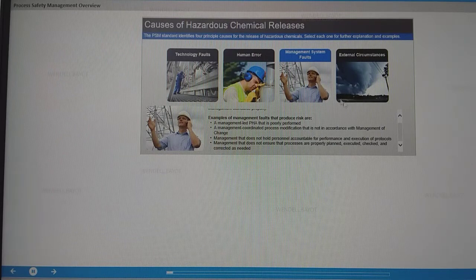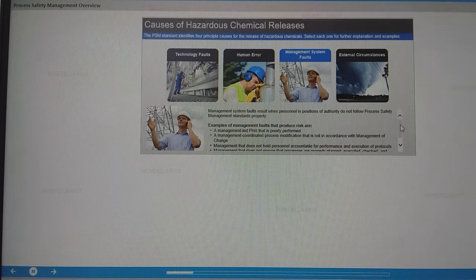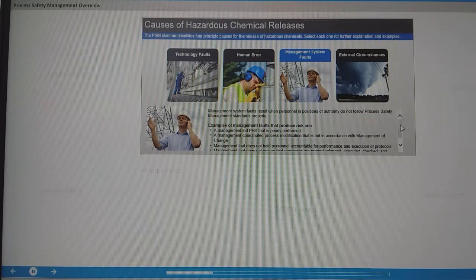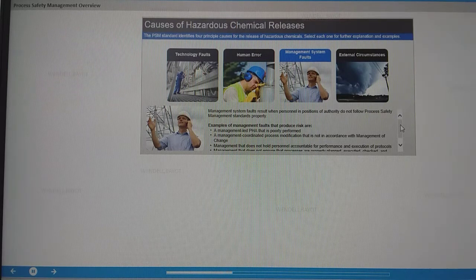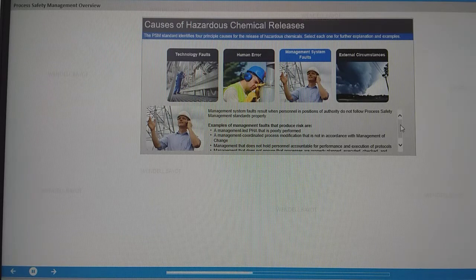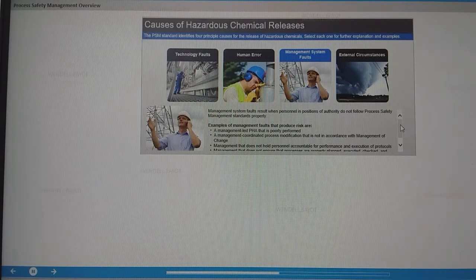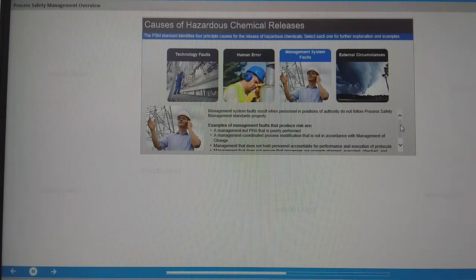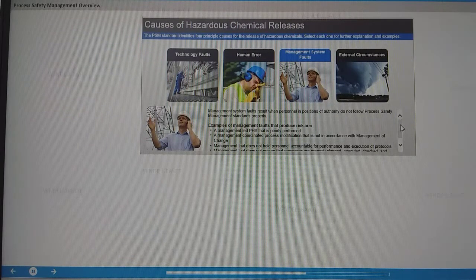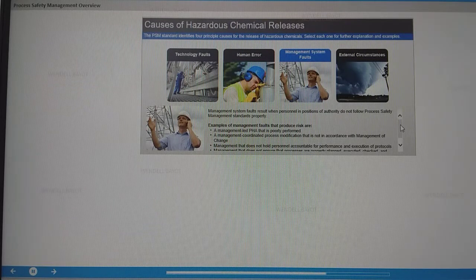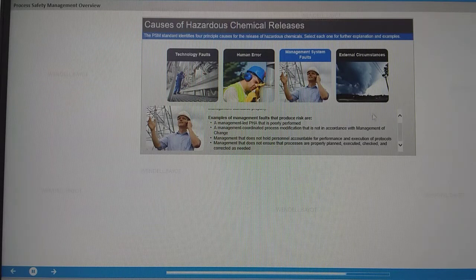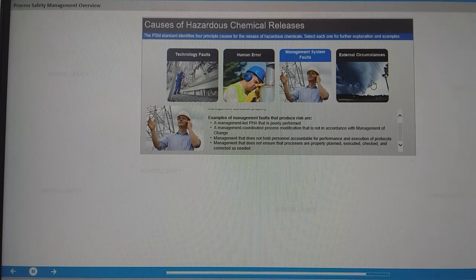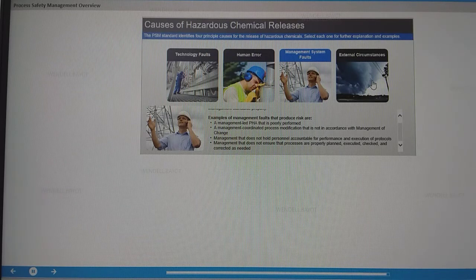Management system faults result when personnel in positions of authority do not follow process safety management standards properly. Examples of management faults that produce risk are a management-led PHA that is poorly performed, a management-coordinated process modification that is not in accordance with management of change, management that does not hold personnel accountable for performance and execution of protocols, and management that does not ensure that processes are properly planned, executed, checked, and corrected as needed.